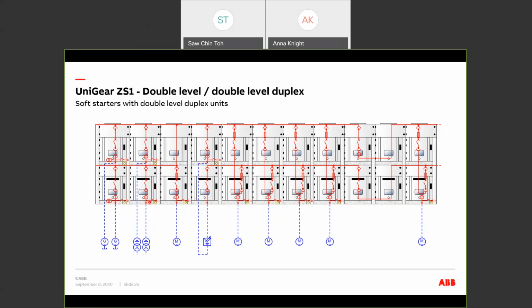Take, for example, the supply coming in from the transformers. This supply will then feed into one of the outgoing feeders, and the feeder will feed into the VSD. The VSD, instead of starting the motor directly, will feed through the start bus of the motors. So from the start bus, switching on the contactor unit, it will switch on the motor. When the motor reaches full speed, the start contactor will then switch to the run contactor. So the motor will continue to take the supply from these bus bars and continue to run. The VSD will then switch to start the rest of the motors one by one and complete the whole switching process. In this arrangement, it's actually a space-saving solution for the customer as well as cost-saving. Instead of buying one VSD for each motor, you're only using one VSD for 4 motors.